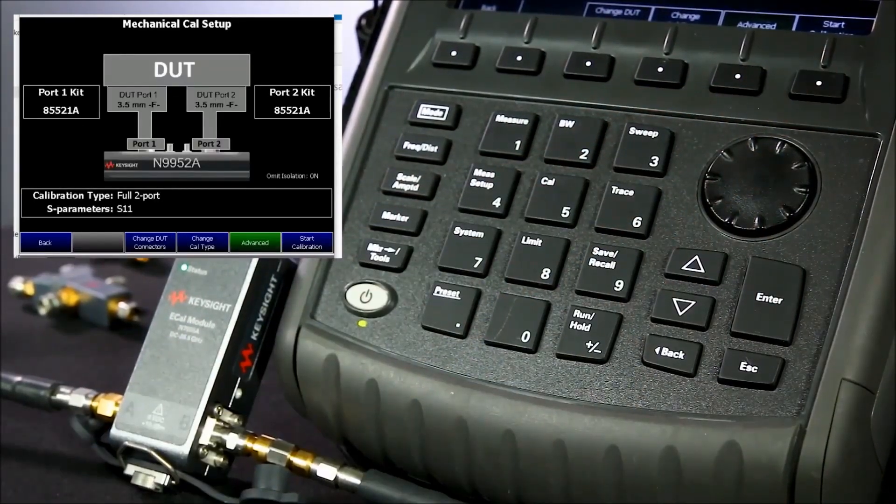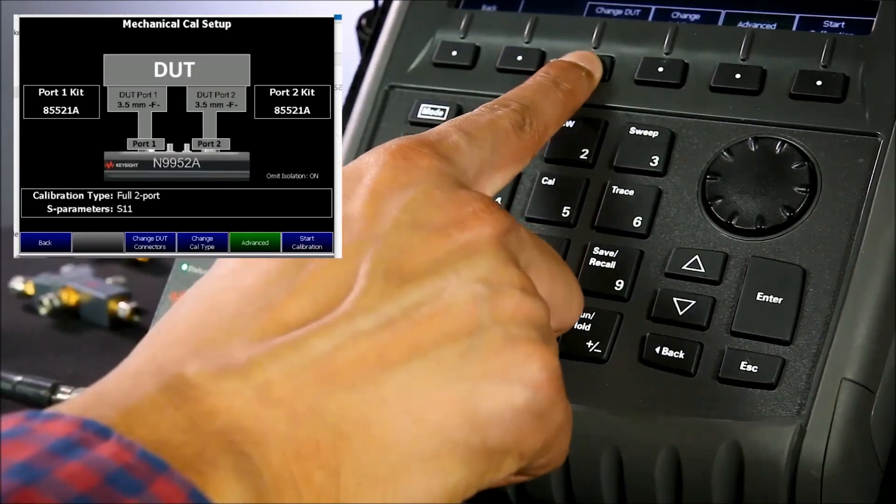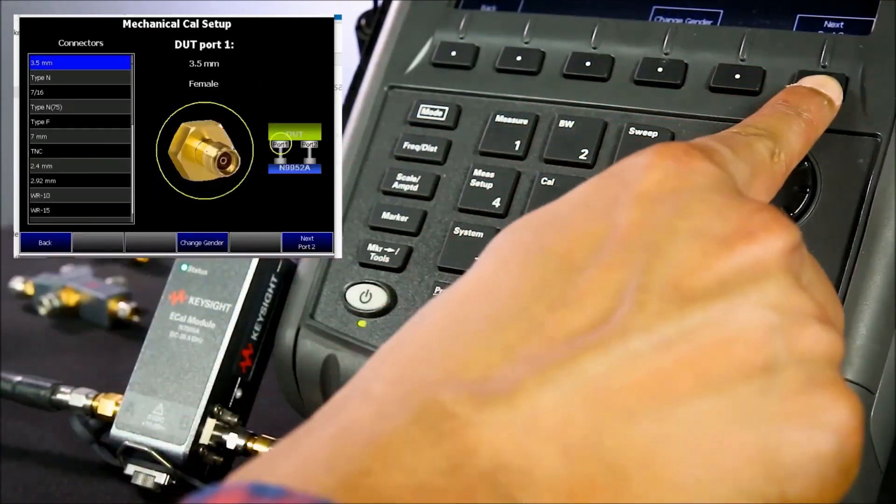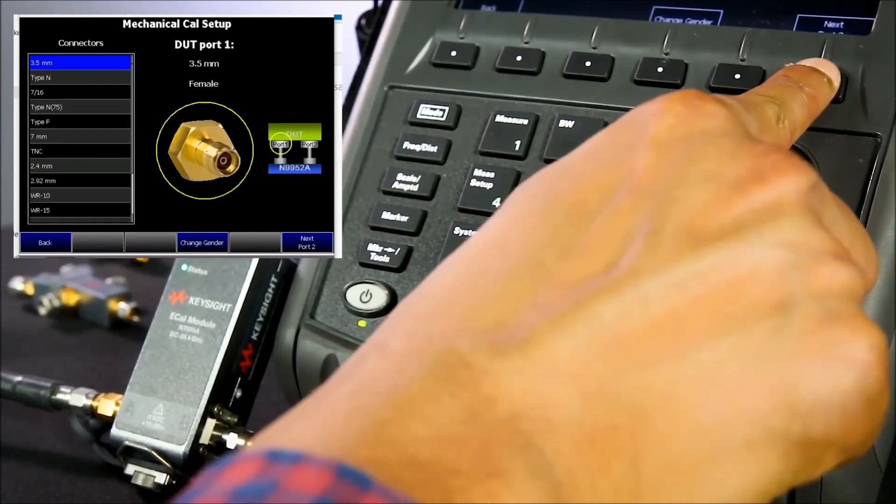We need to make sure that the correct DUT connectors are selected, and in this case, the e-CAL module has a 3.5mm female on port one. Then select next, port two, and a 3.5mm male on port two, so I will change the gender.